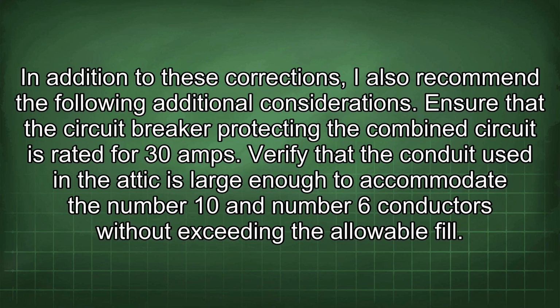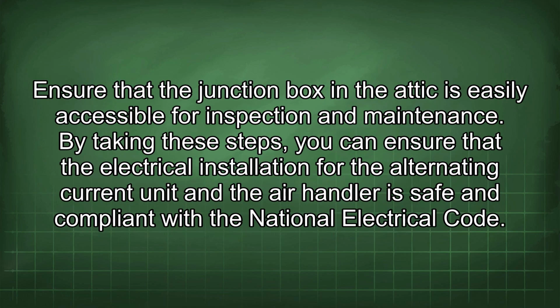In addition to these corrections, I also recommend the following additional considerations. Ensure that the circuit breaker protecting the combined circuit is rated for 30 amps. Verify that the conduit used in the attic is large enough to accommodate the number 10 and number 6 conductors without exceeding the allowable fill. Ensure that the junction box in the attic is easily accessible for inspection and maintenance. By taking these steps, you can ensure that the electrical installation for the alternating current unit and the air handler is safe and compliant with the National Electrical Code.